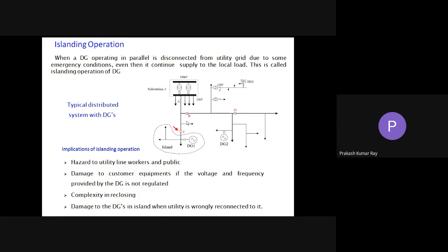So why are we most concerned about this? Because when DG1 is connected to the grid, the operating condition - frequency, voltage, phase angle, rotor angle and other parameters - are something different. But when it is suddenly isolated from the grid, the local load may be less compared to the grid connected mode, so the electrical parameters like frequency and voltage at the load point will change suddenly, affecting the local loads.